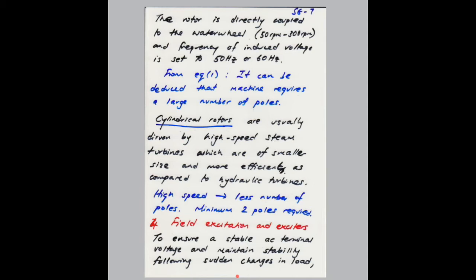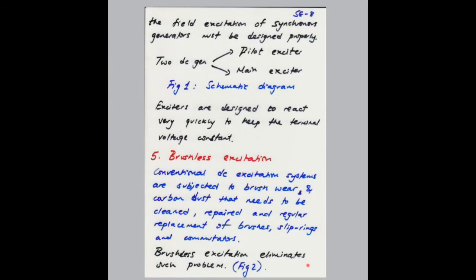by basically having a feedback control. And if there is, for example, sudden changes in load, or your machine is subjected to a fault on the system, then your exciter system will basically operate its control to try and counteract the effect of the change in load or the fault on the system to maintain the terminal voltage to its required value, right? So these exciters are designed to react very quickly to basically keep the terminal voltage constant.